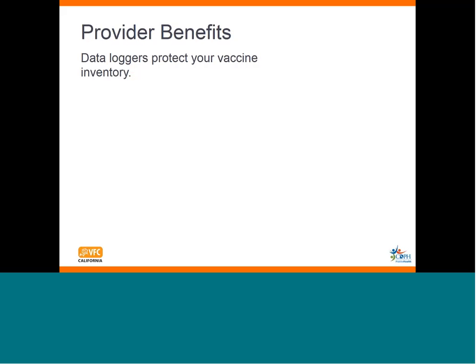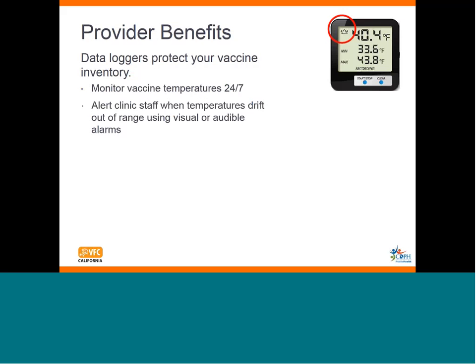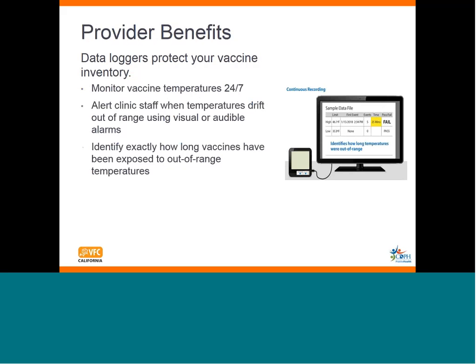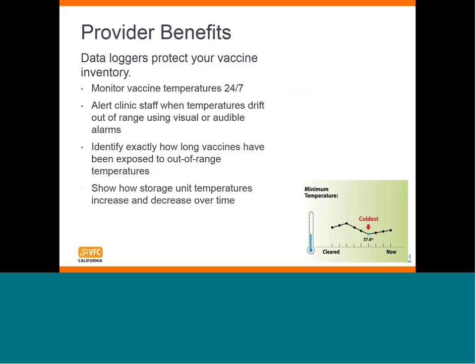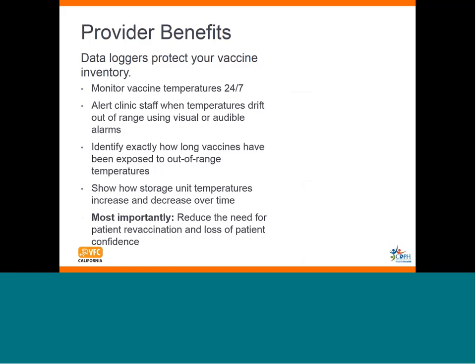We wanted to remind you of the benefits of using digital data loggers other than the fact that it will protect your vaccine inventory. We know that digital data loggers will monitor your vaccine temperatures 24 hours a day, 7 days a week. Another nice feature is it will provide alarm alerts for clinic staff of any temperature excursions. Also, it will determine how long vaccines have been exposed to out-of-range temperatures. And it will also let you know how a storage unit's temperatures increase and decrease over time. The most important thing that we like about digital data loggers is it will reduce the need for patient revaccination and loss of patient confidence.